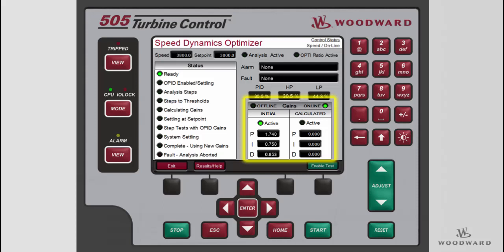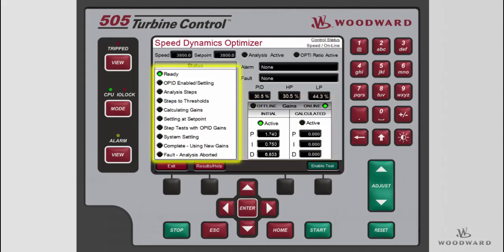Once the test is enabled, the initial gains are active through the analysis mode. When the setpoint step mode is active, the calculated gains become active. The status LEDs on the left-hand side of the page indicate what part of the sequence the optimizer test is currently in. The completed LED indicates that the test was successful, and the speed PID will continue to control at the initial setpoint with the newly calculated gains while the test is in the complete state. When the test is complete, the user can decide to accept or reject the calculated gains. If no decision is made, the test is automatically reset after a timeout period and the gains will revert to the initial gains.